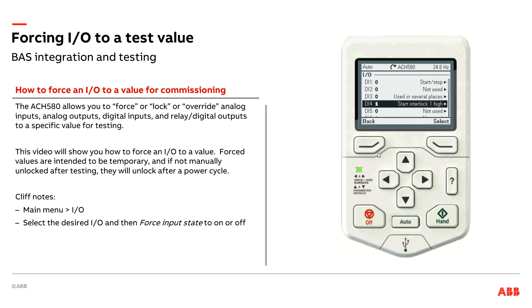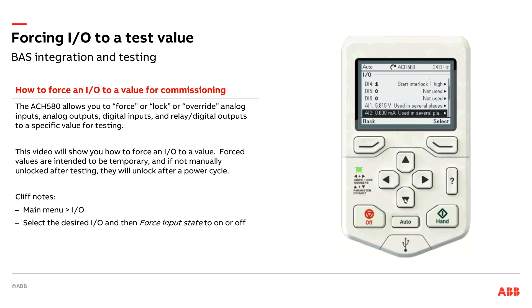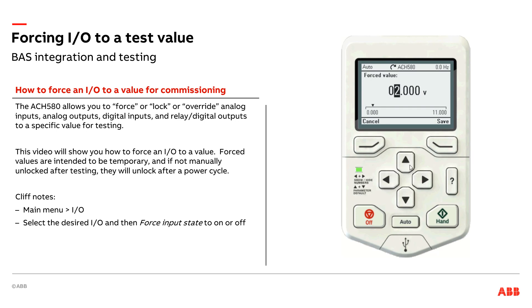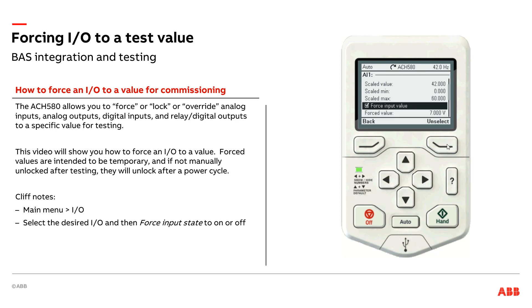Let's take a look at the analog inputs. Let's say I wanted to simulate what happens when I get a 70% command — so a 7-volt command, because I'm set up for 0 to 10 volts right now. I can come down here and force my analog input to simply be 7 volts, or whatever value I'd like to test. You can see that now my command is 42 hertz, because that is 70% of 60 hertz with my drive set up for a 60 hertz network. I'll unselect that and release it so it's no longer forced.